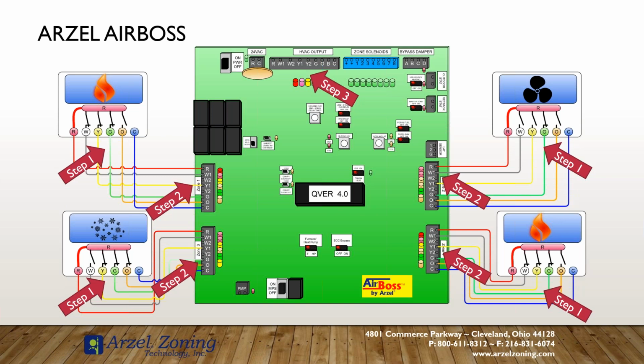So once we start verifying those calls, we can determine what is or isn't working appropriately. And then we can break that down into something that's more bite-sized, more understandable. So instead of trying to wrap our head around 4 thermostats, we can focus on one thermostat at a time, verify it's doing what it says it's doing, verify the board is receiving it, and then we can move to the next. And then once we verify that one, we move to the next. Once that's verified, we move to the next. And once those are verified, we now move to our HVAC outputs, which are a thermostat in relationship to the equipment.